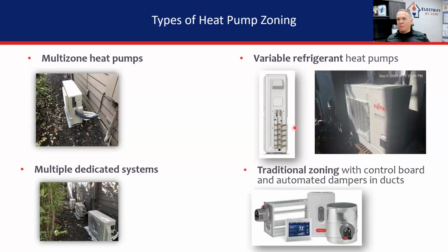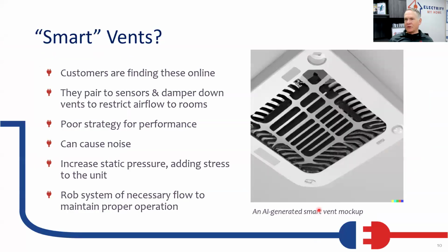And then we've got the traditional zoning with control boards and automated dampers, and some of these inverter heat pump technology companies have zone controls that work with their communication algorithms, but they're not always that successful with it. And then we've got these things called smart vents. I've been seeing these on the HVAC and heat pump Reddit pages recently as a kind of solution. You put a thermostat in one room, and it runs off a battery. The little damper in the grill has a battery in it, and when that room reaches temperature, it just shuts the vent off, which is okay if you've got a balanced system.